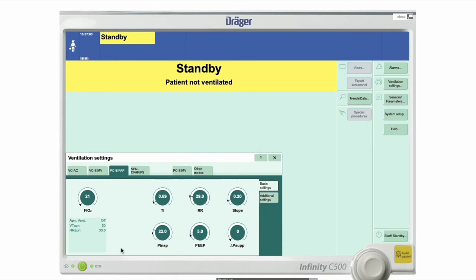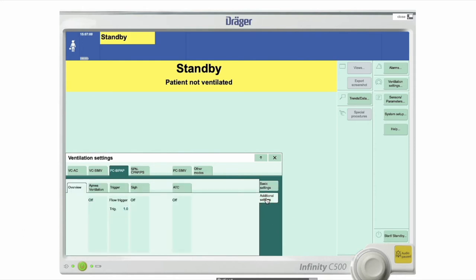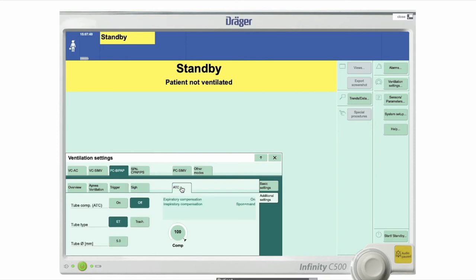So these settings we see here are basic settings. There are some additional settings which we'll discuss in future videos. So there's things like apnea ventilation, which looks like this. There's the flow trigger, which is very important, and of all of them, this is the one thing that you should check anytime you put a patient on the ventilator. There's also a thing called a sigh breath, whether or not we want to use this sigh breath in this patient's ventilation. And there's a thing called automatic tube compensation. And like I said, we'll discuss these in future videos because it's too much to put all that information in here.